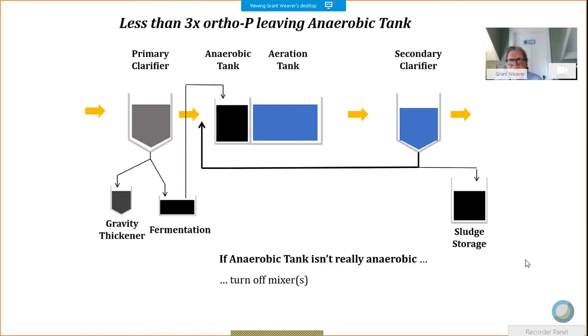I've worked with treatment plants in the Northeast where 1 year they'll use chemicals to adjust the pH, and the next year the price of chemicals changes so that it's cheaper for them to buy chemicals to precipitate the phosphorus. So that's a possibility. The pH in the aeration tank could be too low. That magic number is 6.8. I like a little elbow room, so I like to have a target of 7. Could be not enough dissolved oxygen, not enough DO, but if you're removing ammonia, you probably have enough dissolved oxygen. So that's a possibility, but it's not as likely.